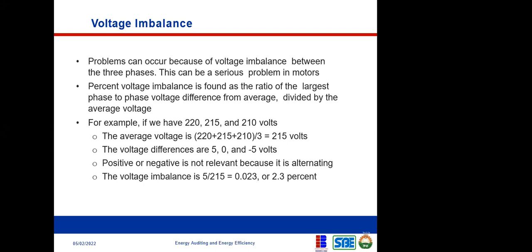Now, first of all, we have to calculate the average voltage. Calculating the average voltage means that we add all these voltages and divide by 3. So we add 220, 215, and 210 together and divide by 3, and we have the average voltage. Once we have this average voltage, the next thing is to find the voltage difference. So if we subtract 215 from 220, what do we get? 5. So the voltage difference for the first line is 5.